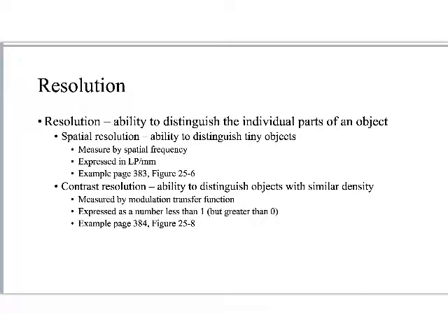If you need an example of what this actual test mechanism looks like, it's right here on the bottom of this page. And that is, if you remember back from some of the labs that we were doing in the spring when I said we need like a redneck spatial resolution template or something, I used some little tiny fine wires on the thing. This is what I was trying to approximate. So I have since asked for budgeting to purchase 2 of these things so that students can see more clearly what we're talking about as we're measuring spatial resolution. And we can actually come up with an actual measurement. This is the number of line pairs that I can see.